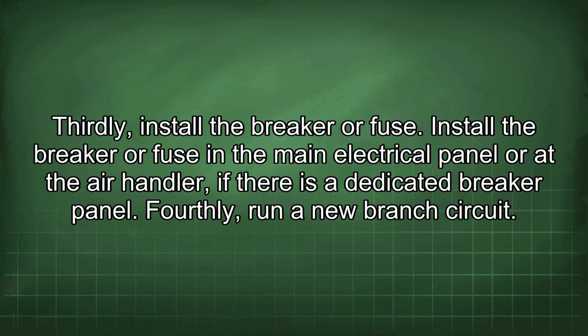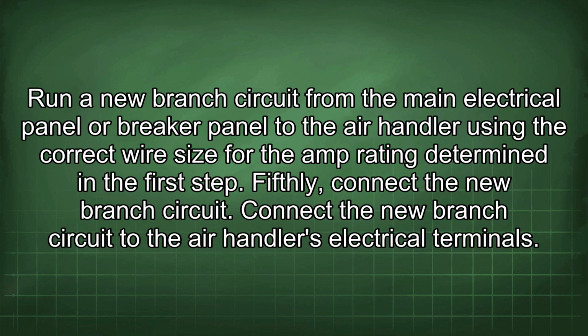Install the breaker or fuse in the main electrical panel or at the air handler if there is a dedicated breaker panel. Fourthly, run a new branch circuit. Run a new branch circuit from the main electrical panel or breaker panel to the air handler using the correct wire size for the amp rating determined in the first step. Fifthly, connect the new branch circuit. Connect the new branch circuit to the air handler's electrical terminals.